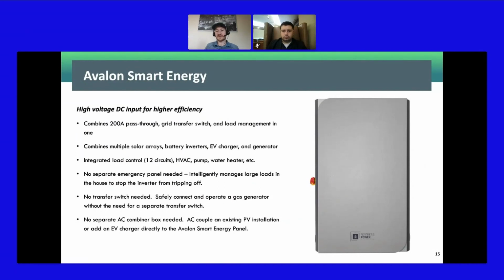And then it also gives you consumption data for the home as well. On top of that, it has automatic load shedding, so if the customer has a 7.6 kilowatt inverter but their air conditioner is a 6-ton unit, you can set the profile so the AC automatically sheds, saving you the time and effort of having a critical loads panel.